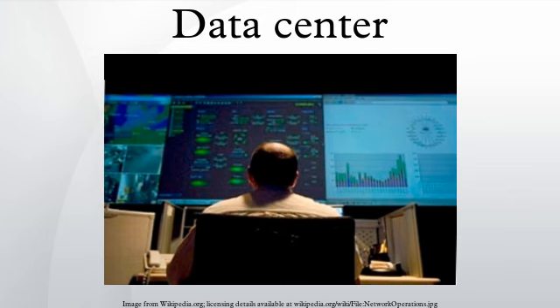Energy use analysis. Often, the first step towards curbing energy use in a data center is to understand how energy is being used in the data center. Multiple types of analysis exist to measure data center energy use. Aspects measured include not just energy used by IT equipment itself, but also by the data center facility equipment, such as chillers and fans. Power and cooling analysis. Power is the largest recurring cost to the user of a data center. A power and cooling analysis, also referred to as a thermal assessment, measures the relative temperatures in specific areas as well as the capacity of the cooling systems to handle specific ambient temperatures.